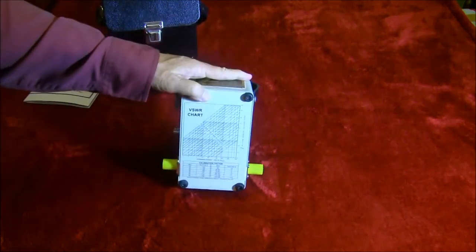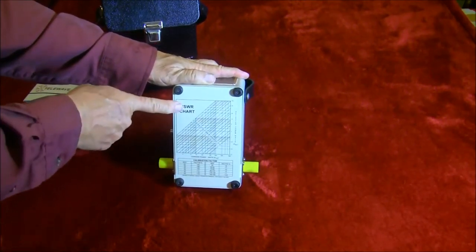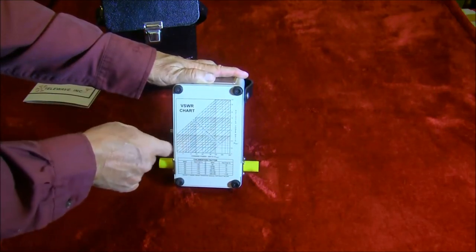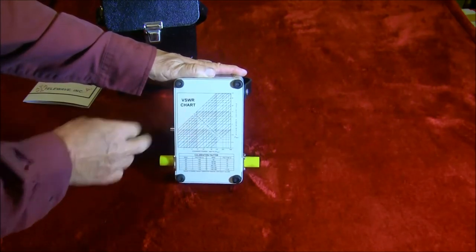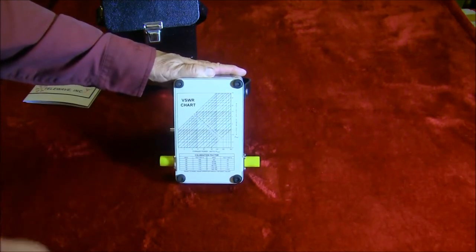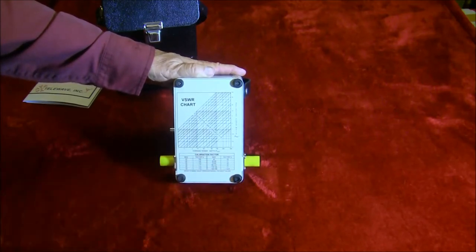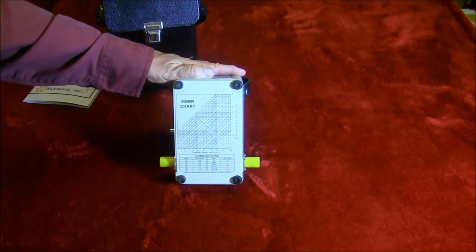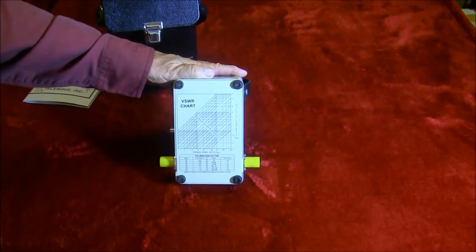On the back, we have charts here. We have a VSWR chart. The VSWR chart is forward power versus reverse power, and you can find the standing wave using that chart. This is also their calibration factor. At various frequencies, this has one directional coupler in it. It's been calibrated, so we know what the factor is to get the exact power level, and we'll go into that in detail.